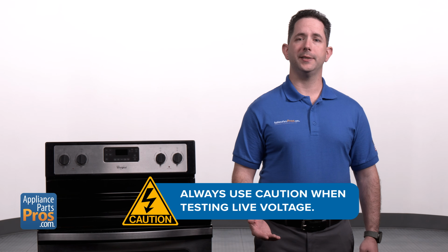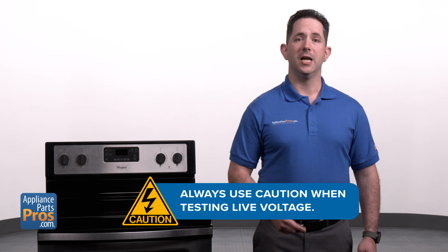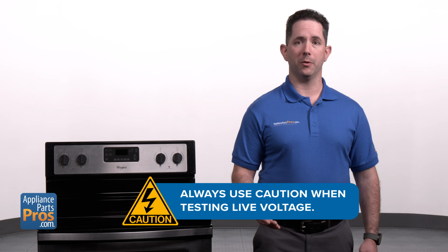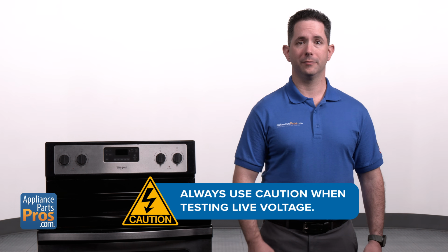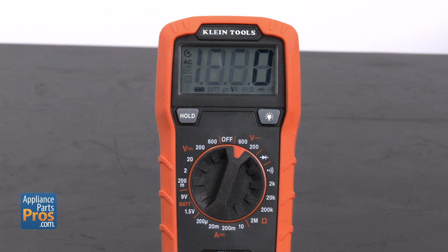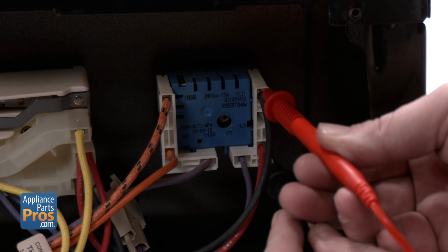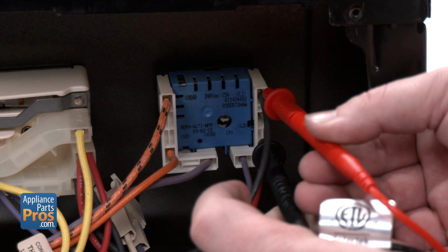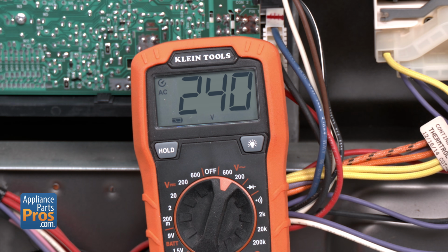Extreme care should always be taken when working around live voltage, since it can result in serious injury. If you're not comfortable testing live power with a multimeter, do not continue. Set your multimeter to volts AC, indicated by a V with a squiggly line. Place one probe on the black wire at terminal L1 and the other probe on the red wire at terminal L2. You should see about 240 volts AC.